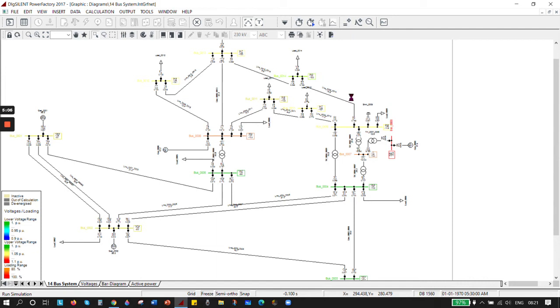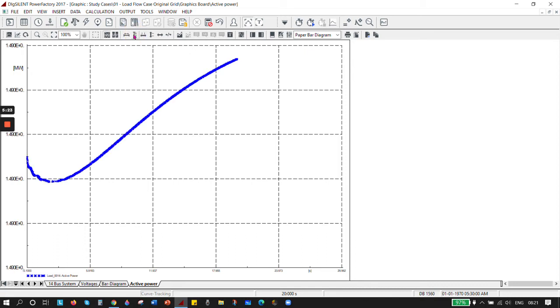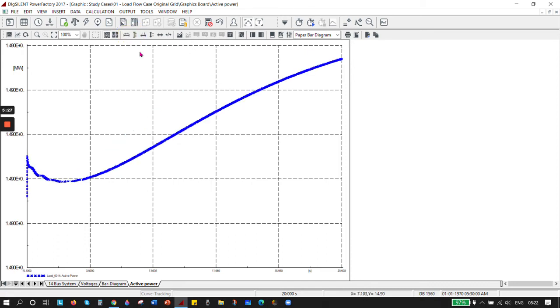Once the simulation is done, it will check all conditions and you will be able to see the result. You might wonder where the result is - just click on the plot to see it. Now, if your plot goes extremely flat like this, it is because you didn't define what type of fault or event it is. This is a common mistake. You need to define what kind of fault or event you want to do.